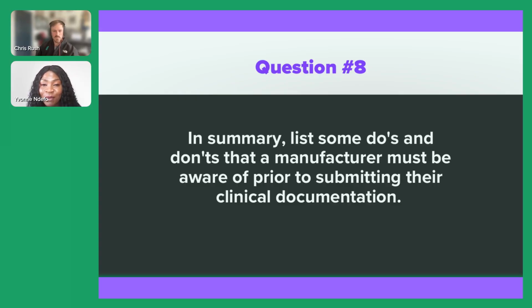So this is something that, maybe now it's getting better, but towards the early stage of the MDR, there was a misconception that because these are legacy devices, they've been in the market, they are not going to be reviewed as per the requirements of the MDR. So don't make that assumption. And then secondly, PMCF has to be done. Whether you're a legacy device or a new device manufacturer or a high-risk device, you need to have a PMCF plan and a PMCF report. You need to make sure that you've provided that as per the MDCG 2020-7 and 2020-8.